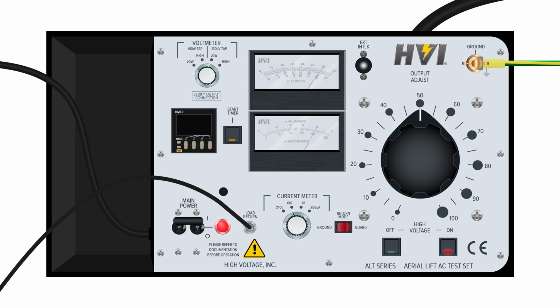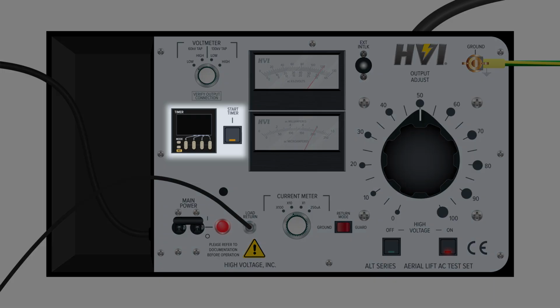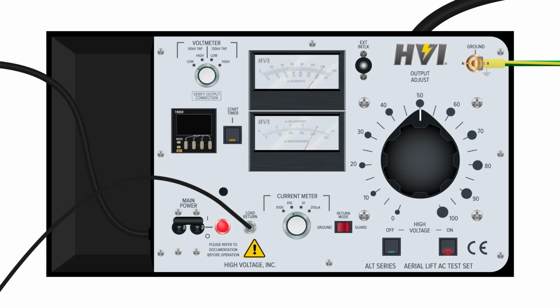Now, set the timer for the desired test duration for the specific test. Timers will vary slightly in operation based on specific models. Refer to the user manual for additional information on the operation of the timers. Maintain the required voltage for the duration of the test. When the timer has counted down to 0, an alarm will sound indicating the test duration is complete.